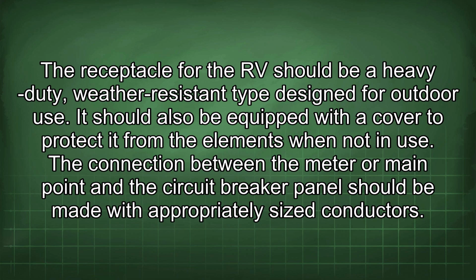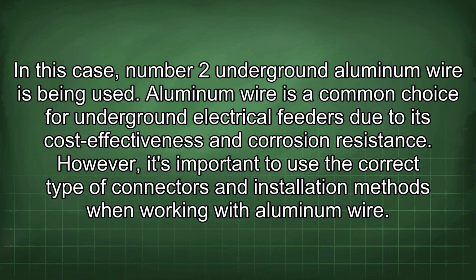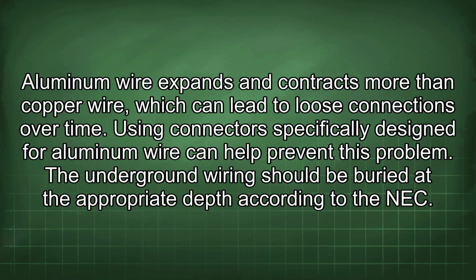The connection between the meter or main point and the circuit breaker panel should be made with appropriately sized conductors. In this case, number 2 underground aluminum wire is being used. Aluminum wire is a common choice for underground electrical feeders due to its cost-effectiveness and corrosion resistance. However, it's important to use the correct type of connectors and installation methods when working with aluminum wire. Aluminum wire expands and contracts more than copper wire, which can lead to loose connections over time. Using connectors specifically designed for aluminum wire can help prevent this problem.